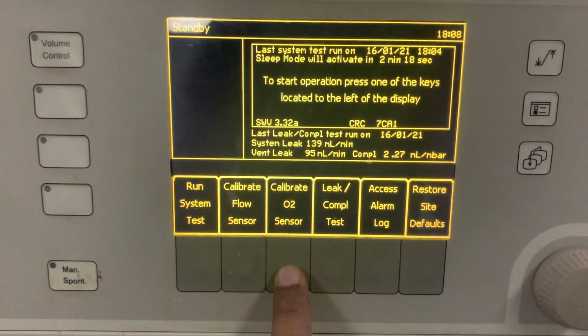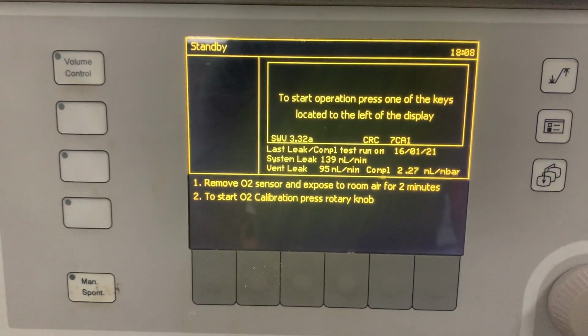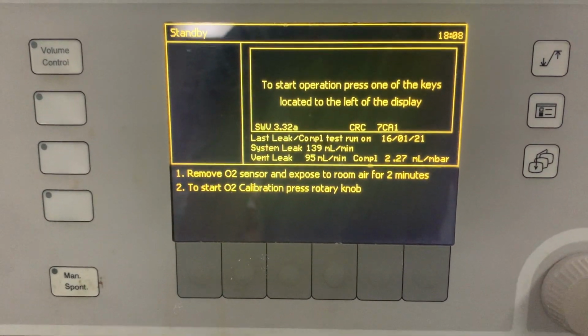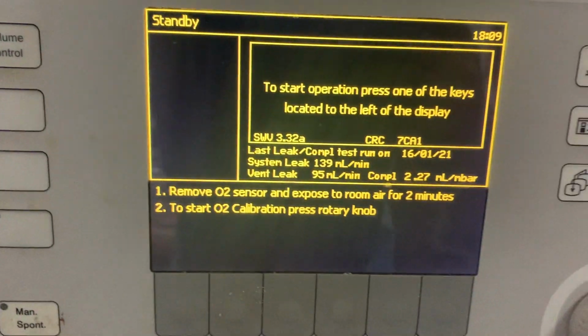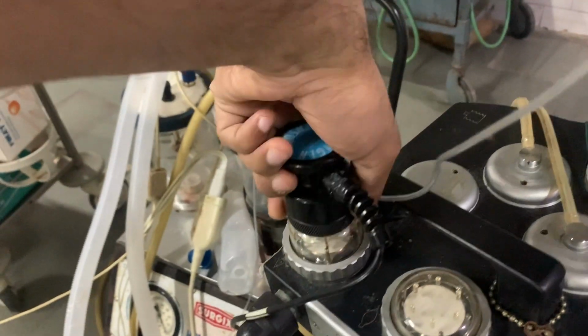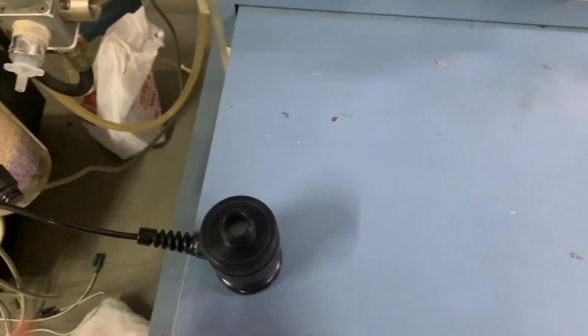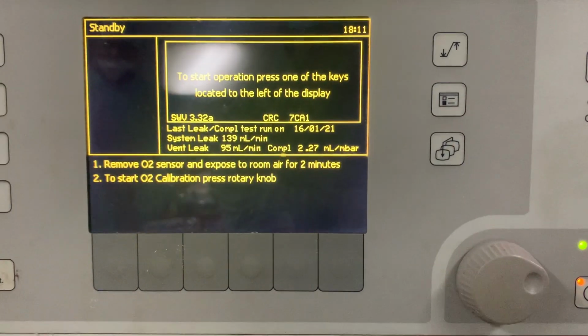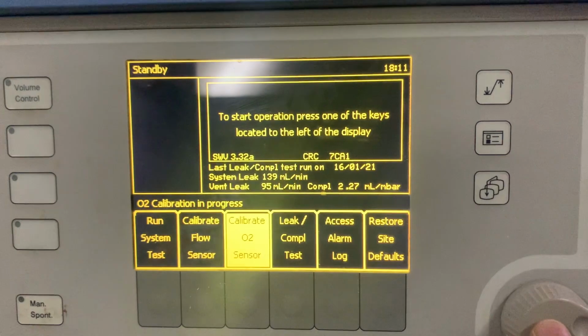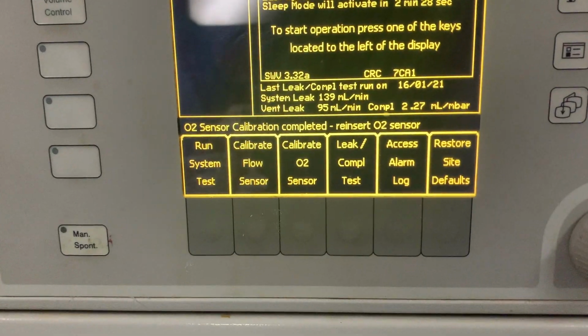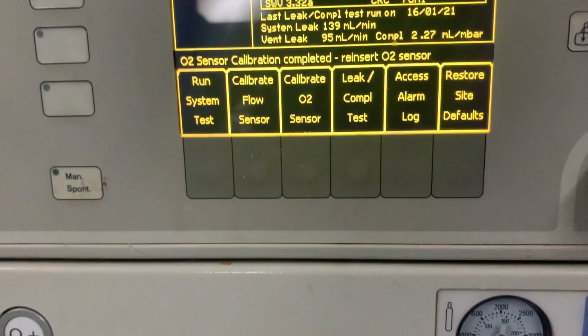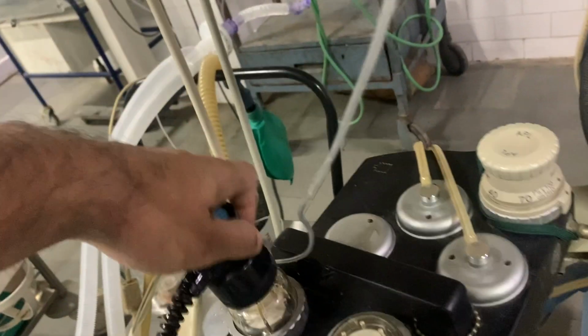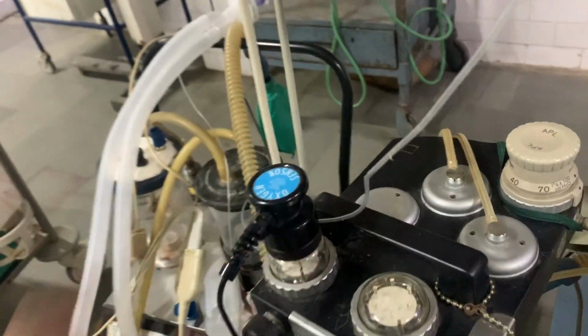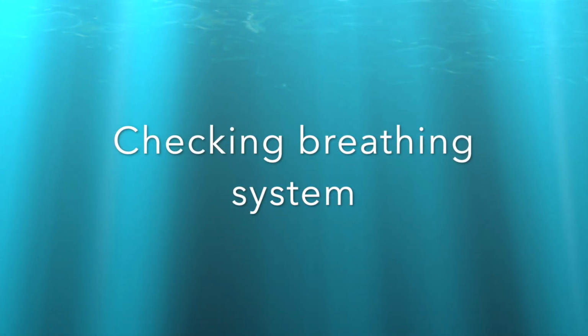For calibration of the oxygen sensor, click on calibrate oxygen sensor. Now remove the oxygen sensor and expose it to room air for at least 2 minutes. Once the calibration is completed, reinsert the oxygen sensor. Next is checking the breathing system.